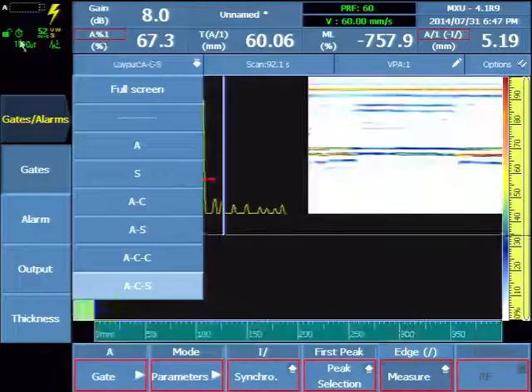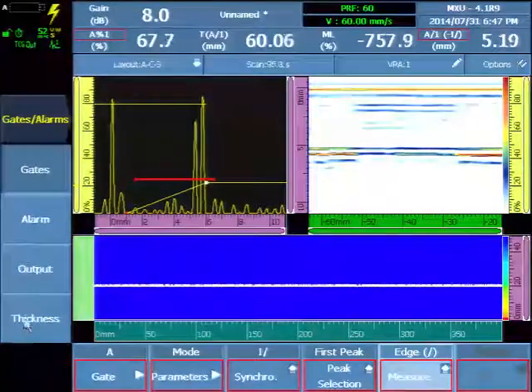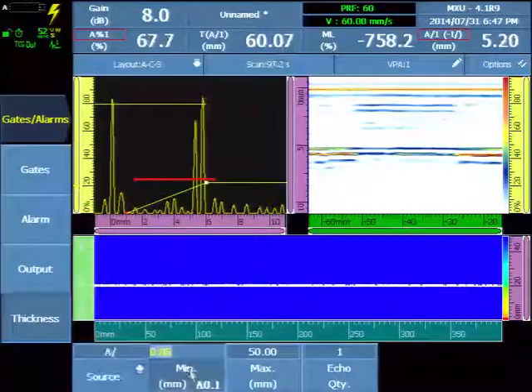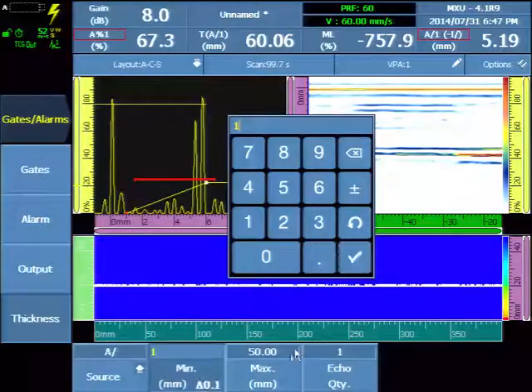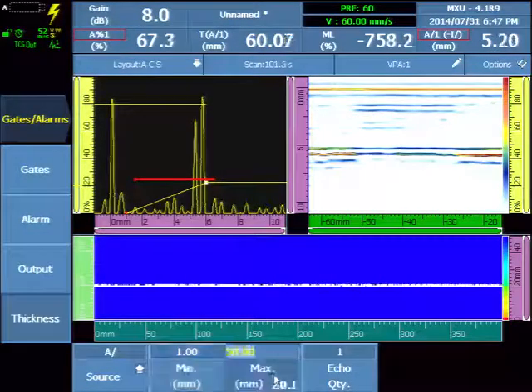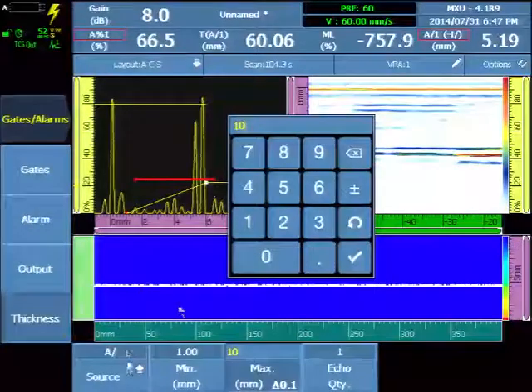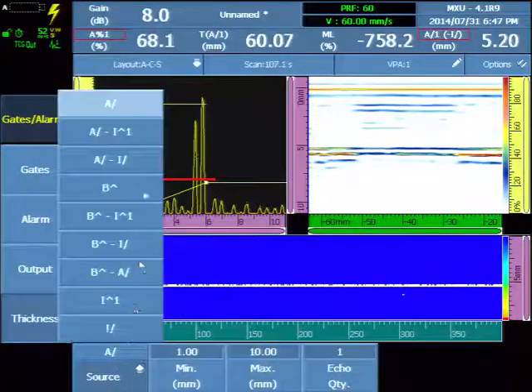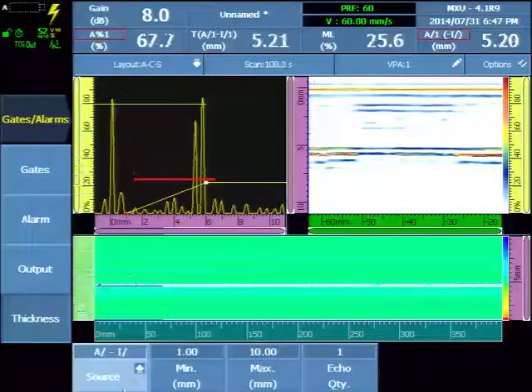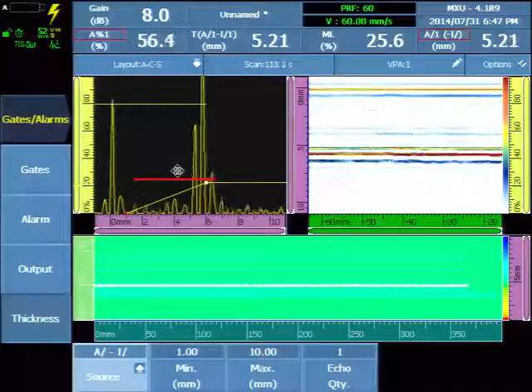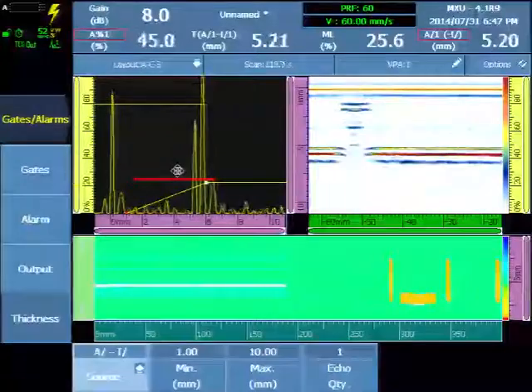We'll enable the C-scan. At this point we're on time so we'll see a scrolling C-scan. We'll enter a thickness for the component of about 1 millimeters to 10. And we will use the A minus I reading for our readings and for the color palette.